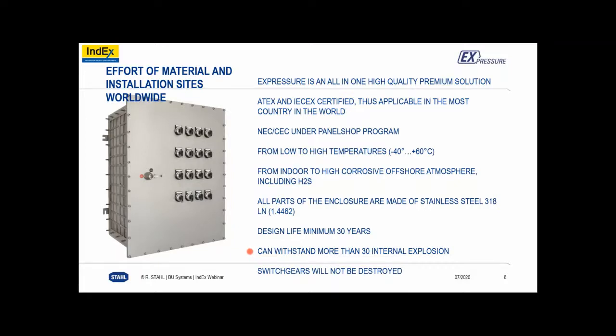This is also one of the big advantages: after an explosion, you simply replace the explosion vents on the sides of the ExPressure, and you see if there was an explosion in the enclosure because the explosion vents are open, and there is really a sign of that. We also have the possibility to give you an electrical solution, so that you get a signal if the explosion vent has been opened.